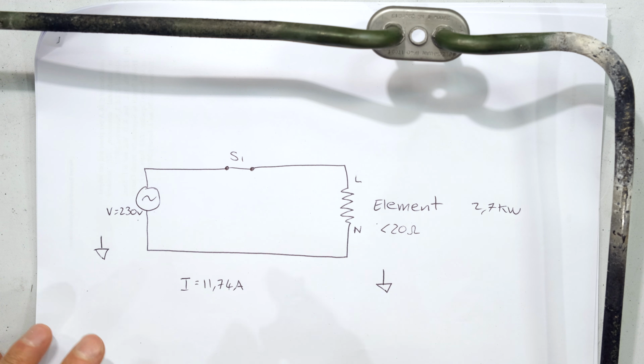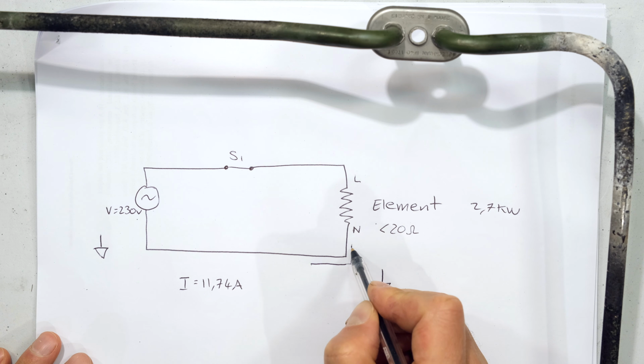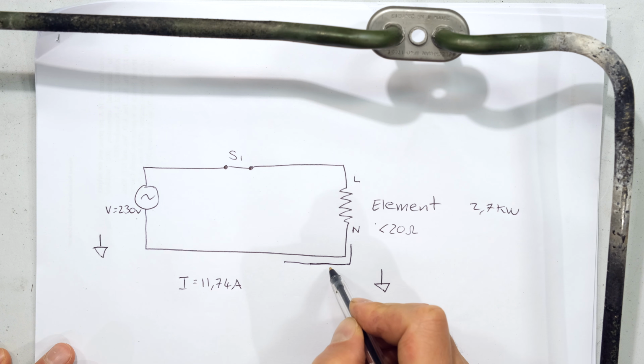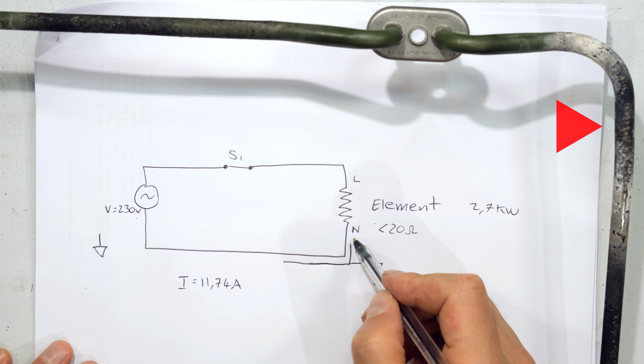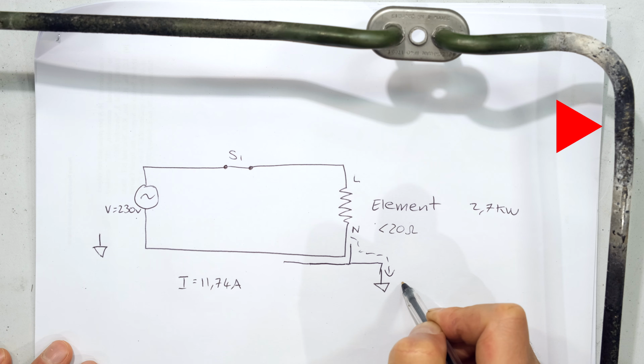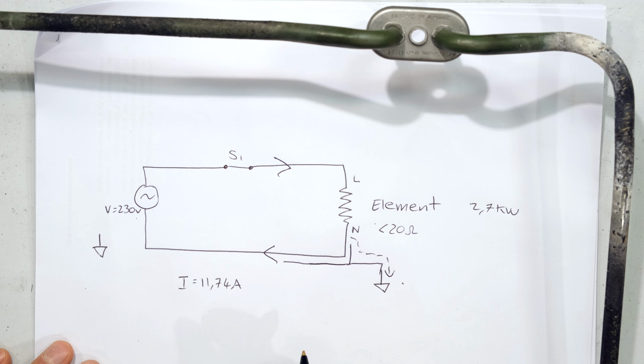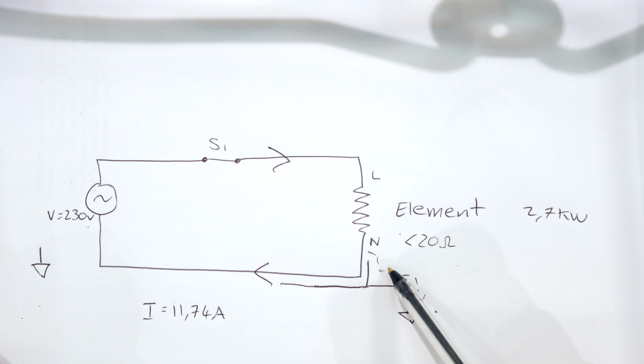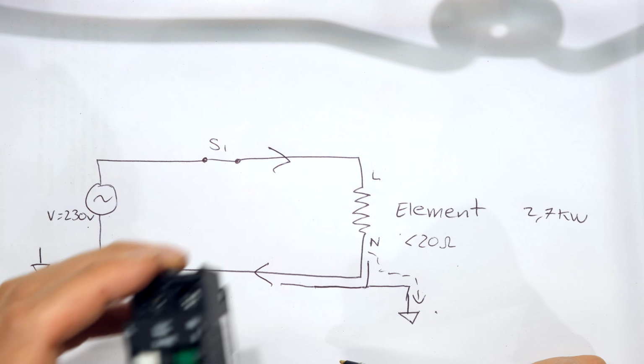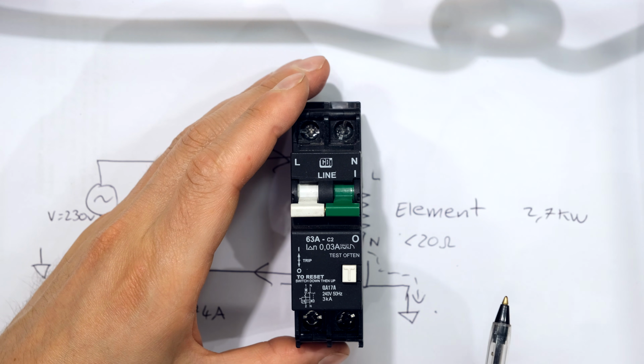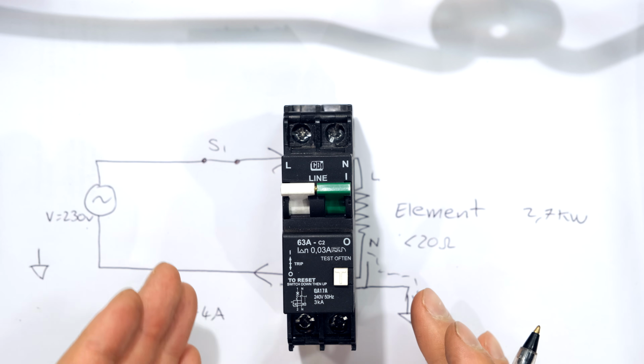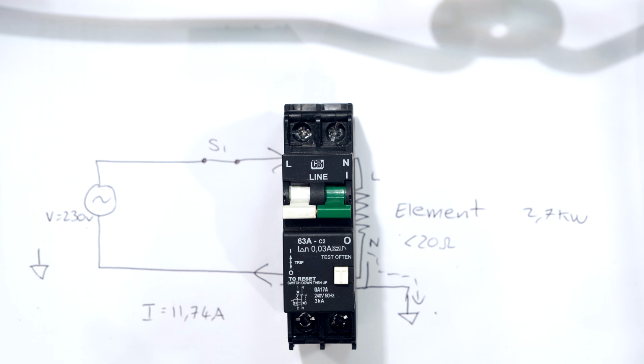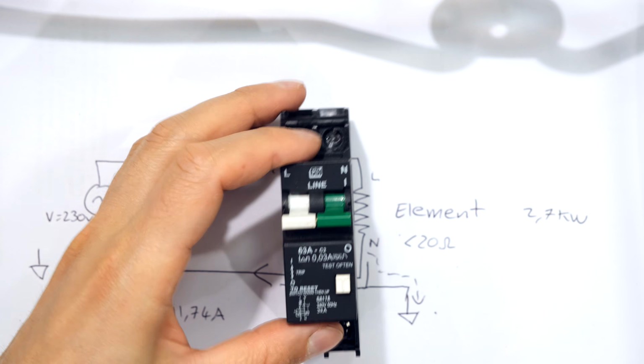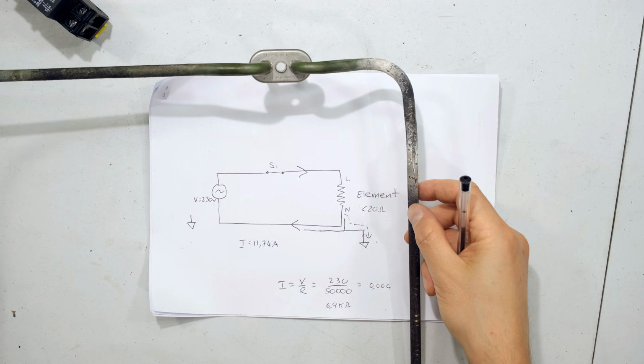Right, so what is happening there is around the wire here, we've got that tube. That tube is connected to earth, and current is actually leaking to earth. That means the current coming in and the current coming out are actually imbalanced. So straight current is going to earth, which means there's an imbalance. And just having a look at the earth leakage circuit breaker or your RCD, if there's a difference of 30 milliamps or more, this will trip. That means the live current is 30 milliamps higher than the neutral current. In the case of this element, as more and more of the insulation breaks down, we get a higher earth leakage current, and when we get that earth leakage current, it will then trip the earth leakage circuit breaker.